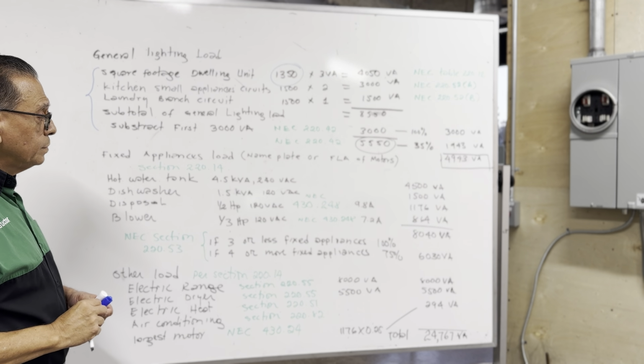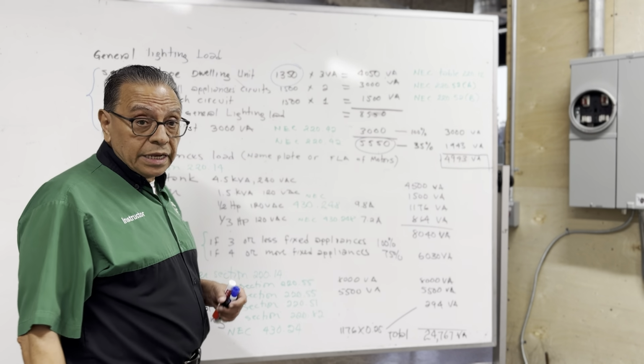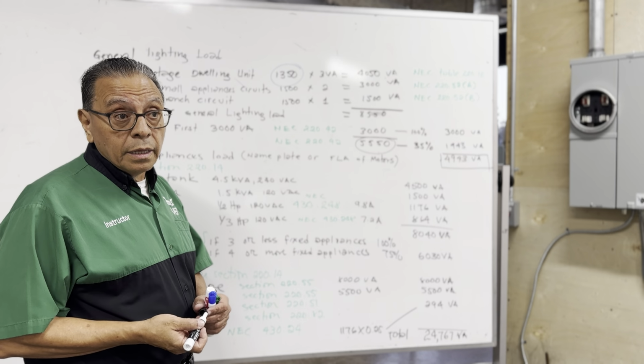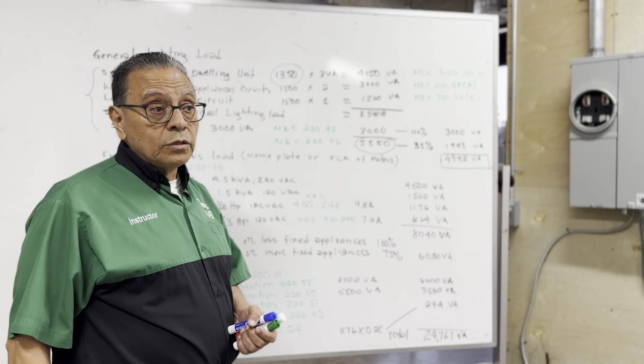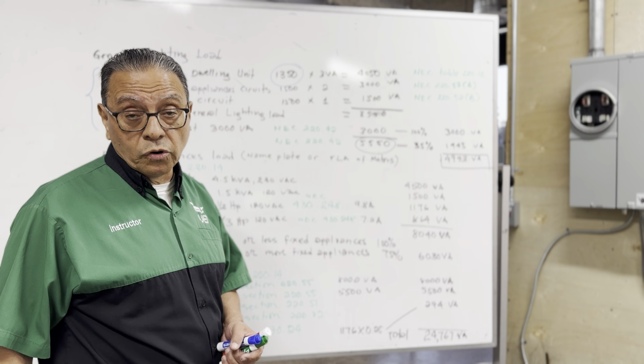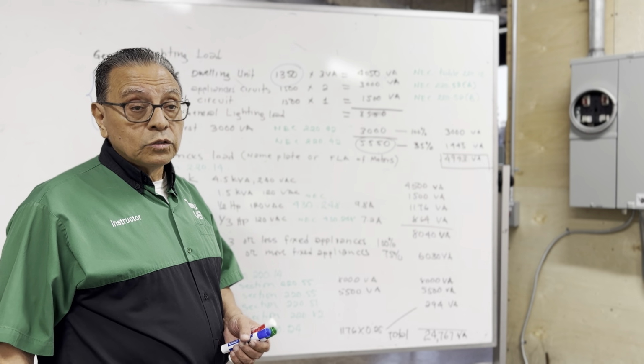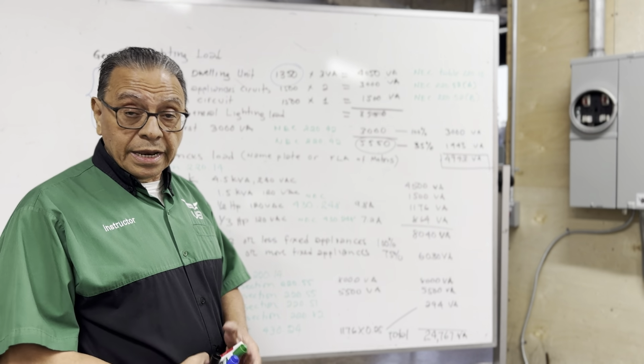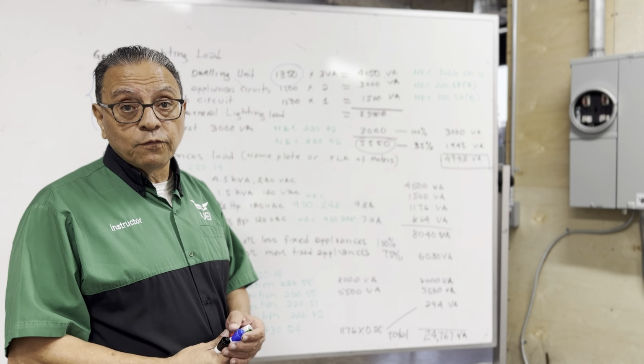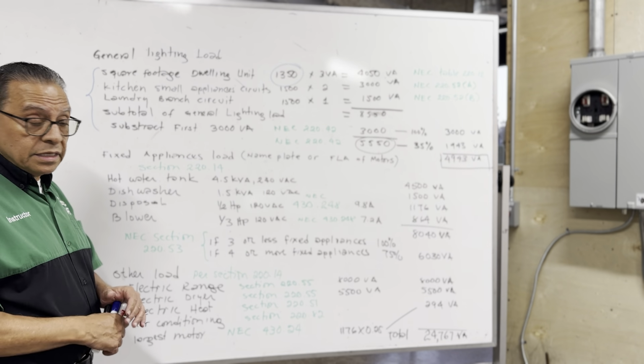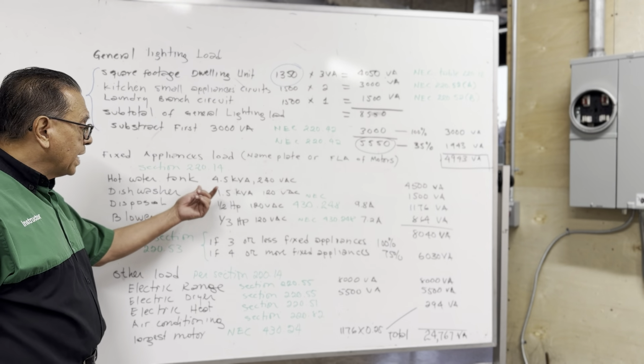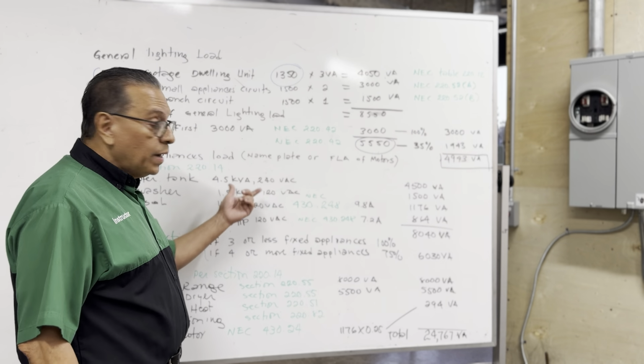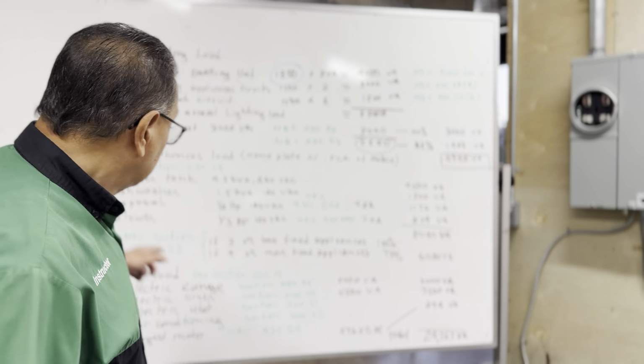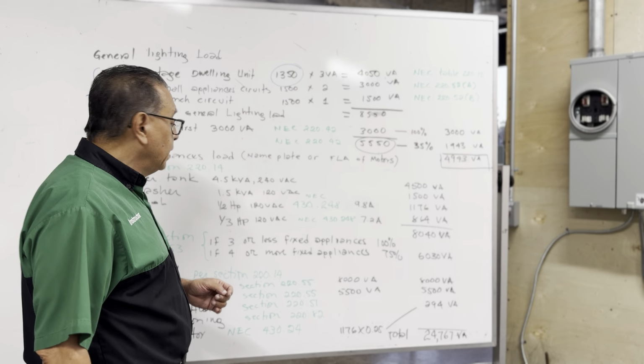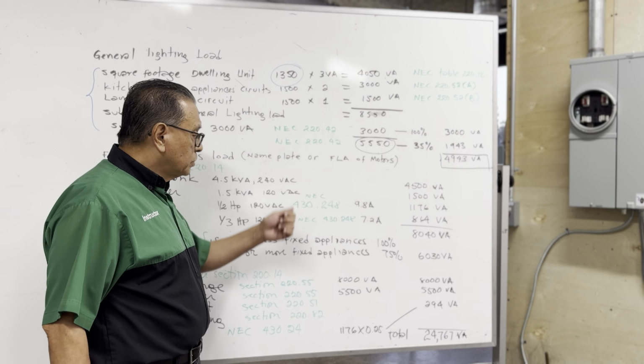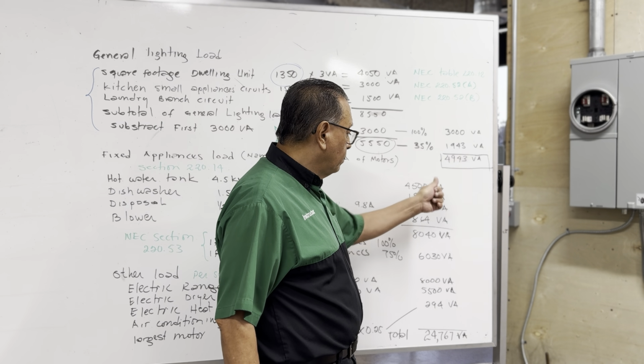For the fixed appliances load, I have two options. I can use the information on the nameplate, or use table 430.248 for single-phase electrical motors, or 430.250 for three-phase electrical motors, and I use the horsepower to find out the full load capacity. In this case, these are single-phase motors, so for the hot water tank, I am using the nameplate. The nameplate in my hypothetical example is telling me that the hot water tank is demanding 4.5 kilovolt ampere at 240 volts. The total is 4,500 volt ampere.